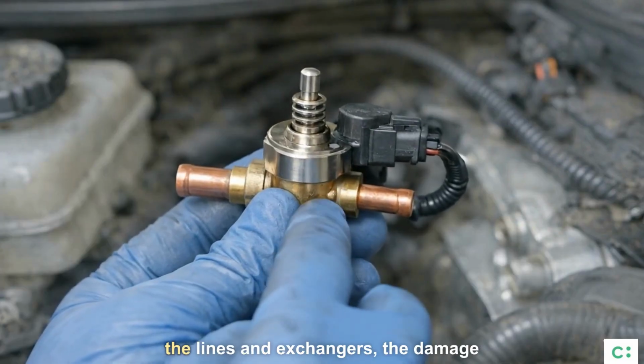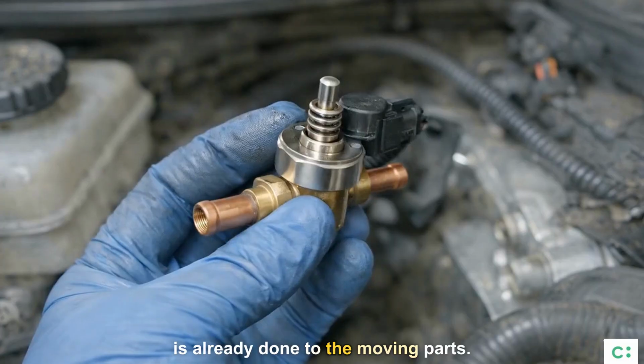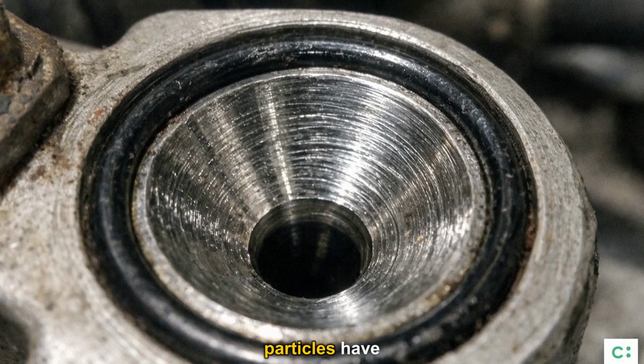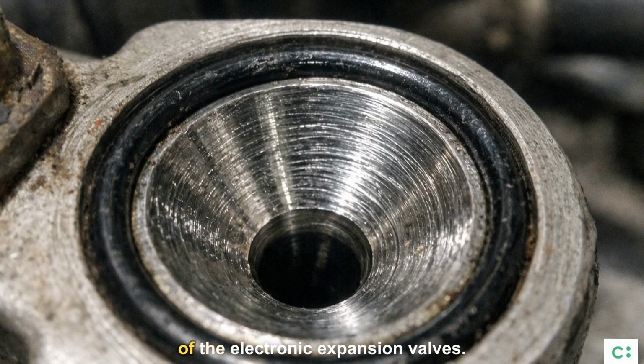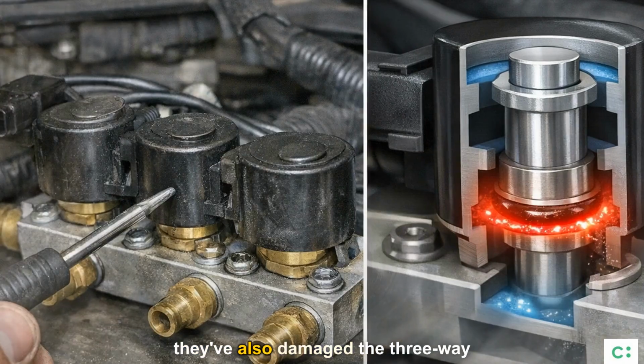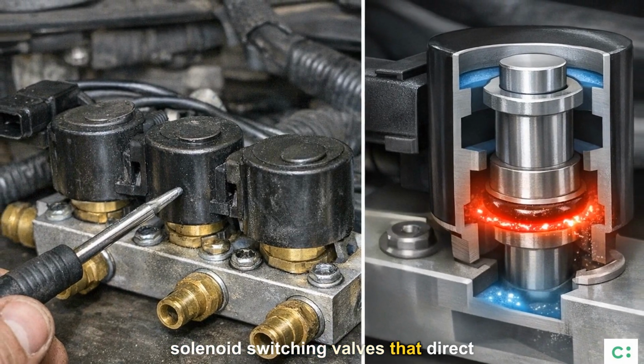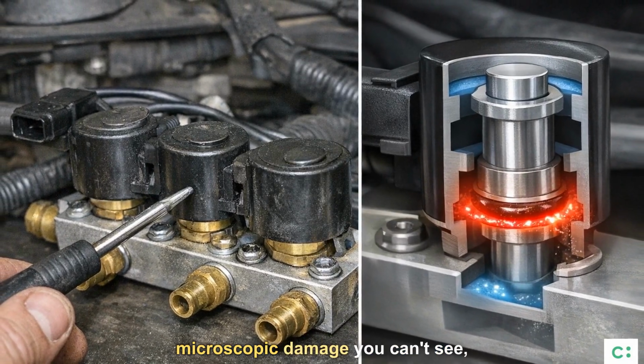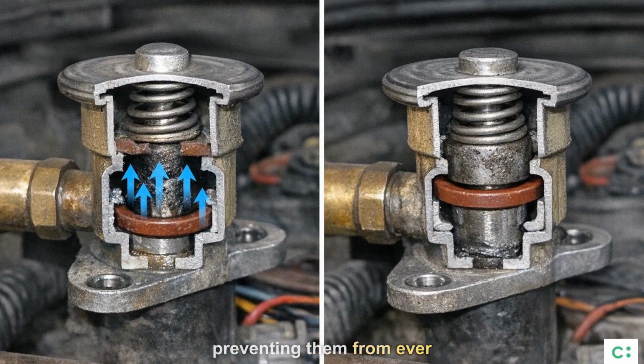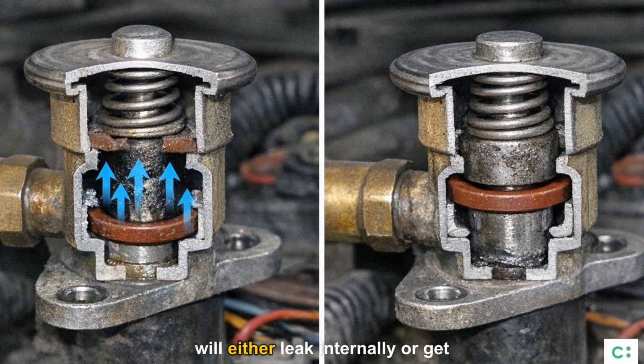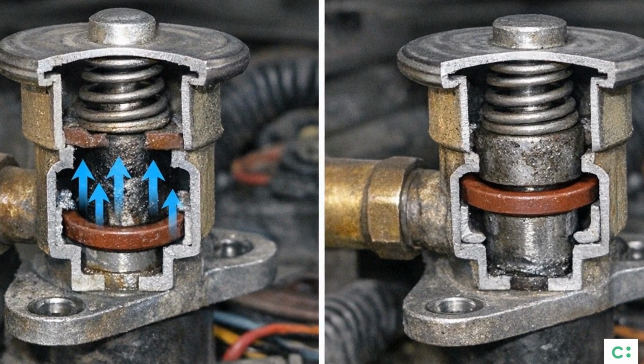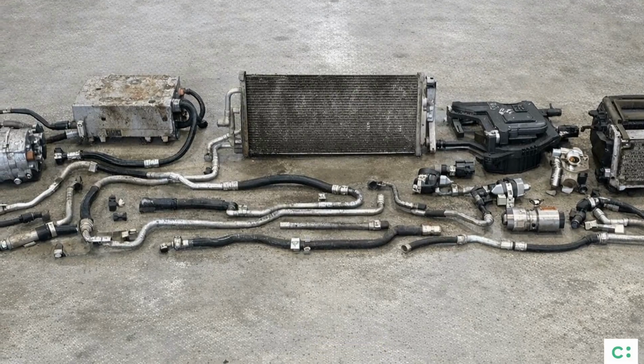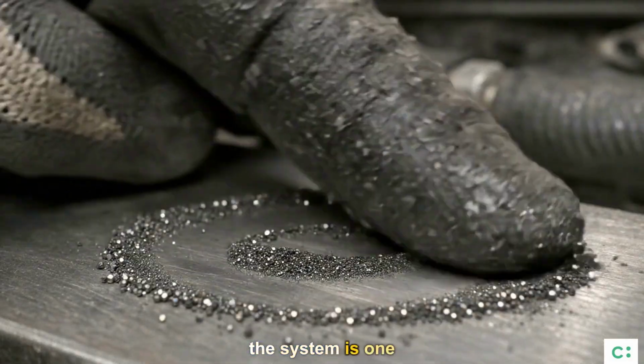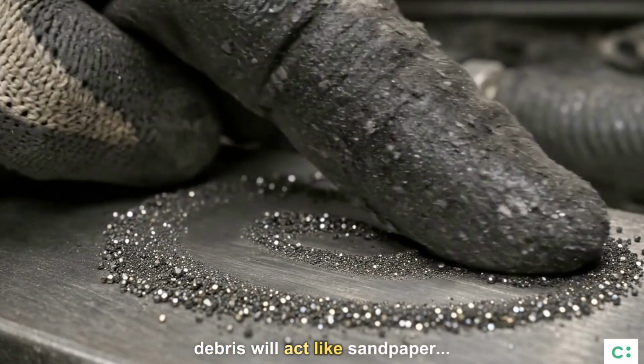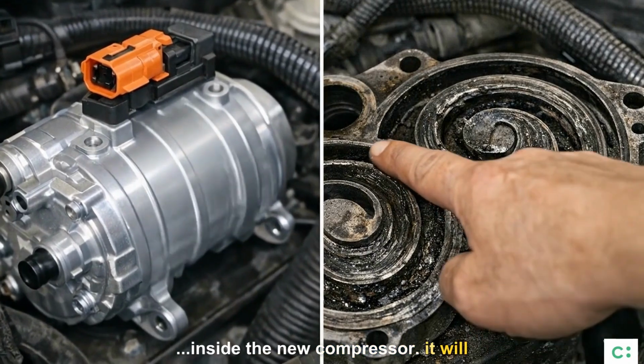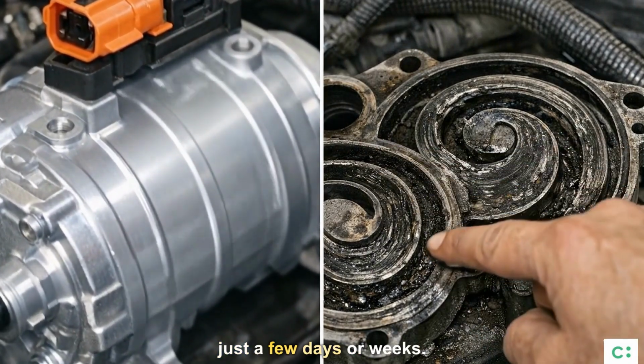Even if you could somehow clean the lines and exchangers, the damage is already done to the moving parts. Those tiny abrasive metal particles have scraped and scored the internal seats of the electronic expansion valves. They've also damaged the three-way solenoid switching valves that direct refrigerant flow. This causes microscopic damage you can't see, preventing them from ever sealing properly again. It means they will either leak internally or get stuck in one position, crippling the system's ability to heat or cool correctly. Because it's impossible to guarantee the system is 100% clean, any leftover debris will act like sandpaper inside the new compressor. It will destroy the replacement, often within just a few days or weeks.